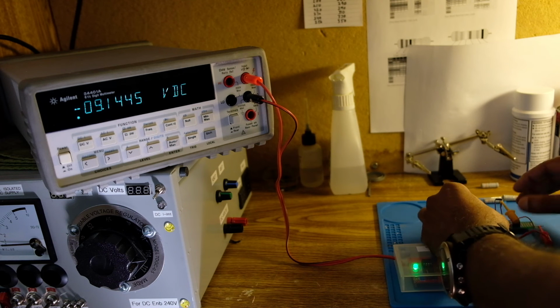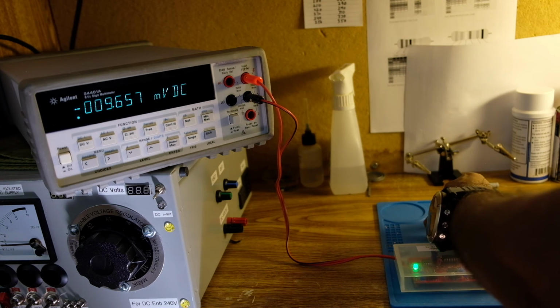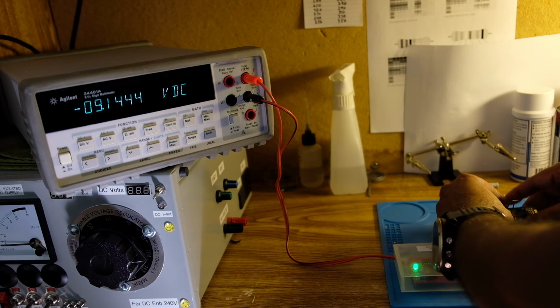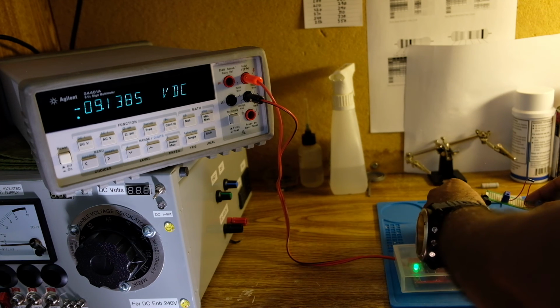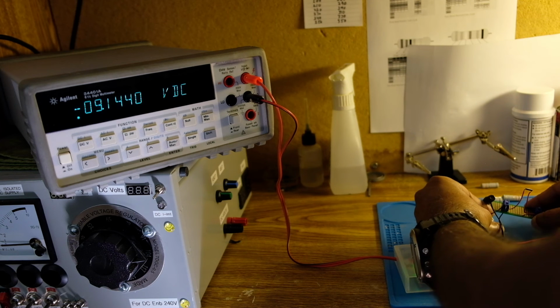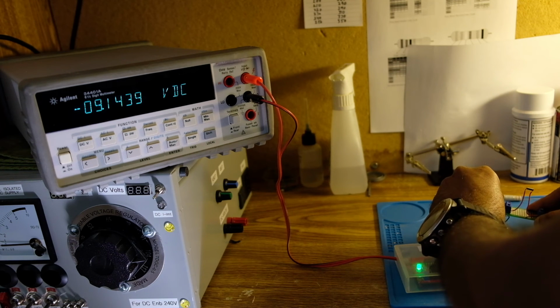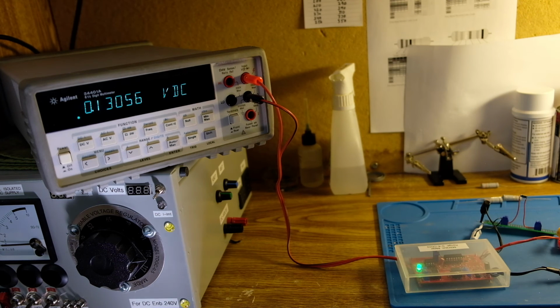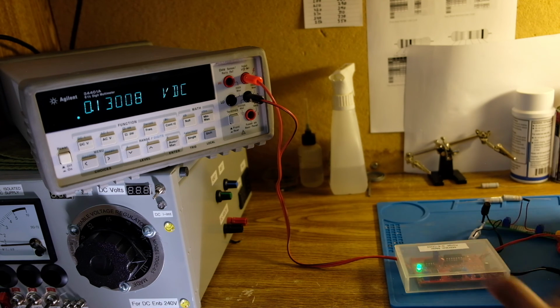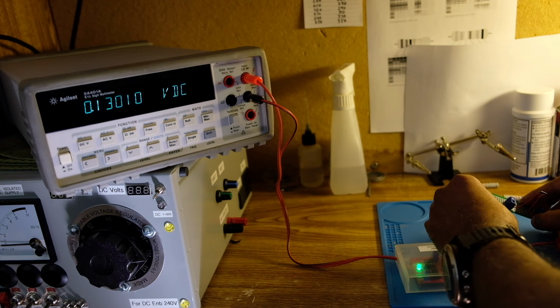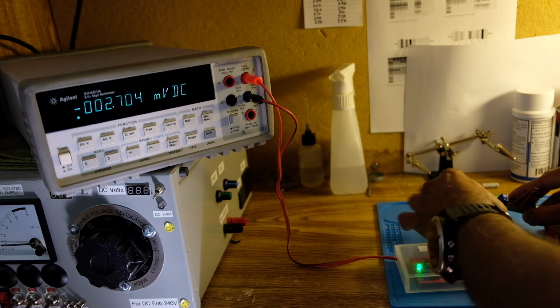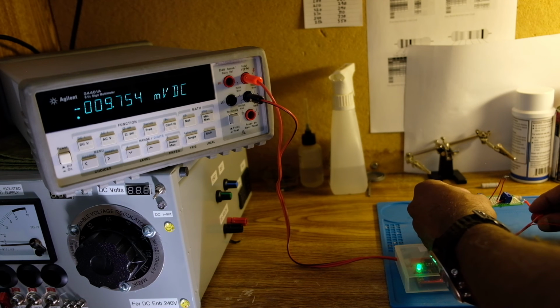You'll see the effect of measuring at different points. The lead resistances—if I measure over here at the right where the source is, you'll see a distinctly different value, and that is 0.13056. That means there's 30 milliohm of extra resistance just in the leads going from here to here, 15 milliohm on each side. These kinds of resistances can play a role if you're really trying to get down to the milliohm level of measurements.